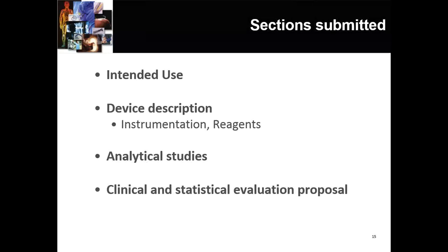So what is a mock submission, nuts and bolts? It's a submission to the agency that is meant to represent what would be incorporated into an actual pre-market submission. But of course, because it's mock, we can focus our attention on those sections that we think are really important, both for the community that would be the submitters as well as FDA as responders. So in the case of this proteomics example, these were the 6 sections submitted.